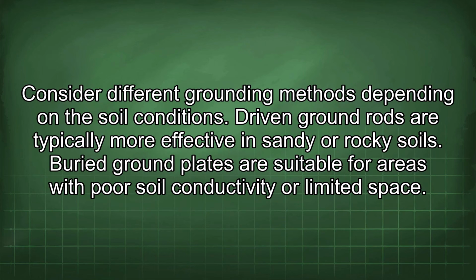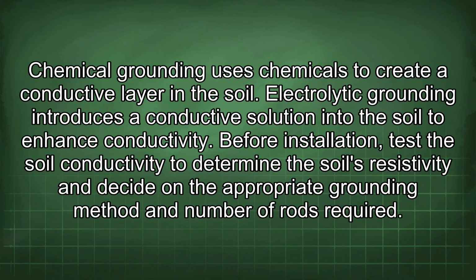Consider different grounding methods depending on the soil conditions. Driven ground rods are typically more effective in sandy or rocky soils. Buried ground plates are suitable for areas with poor soil conductivity or limited space. Chemical grounding uses chemicals to create a conductive layer in the soil. Electrolytic grounding introduces a conductive solution into the soil to enhance conductivity.